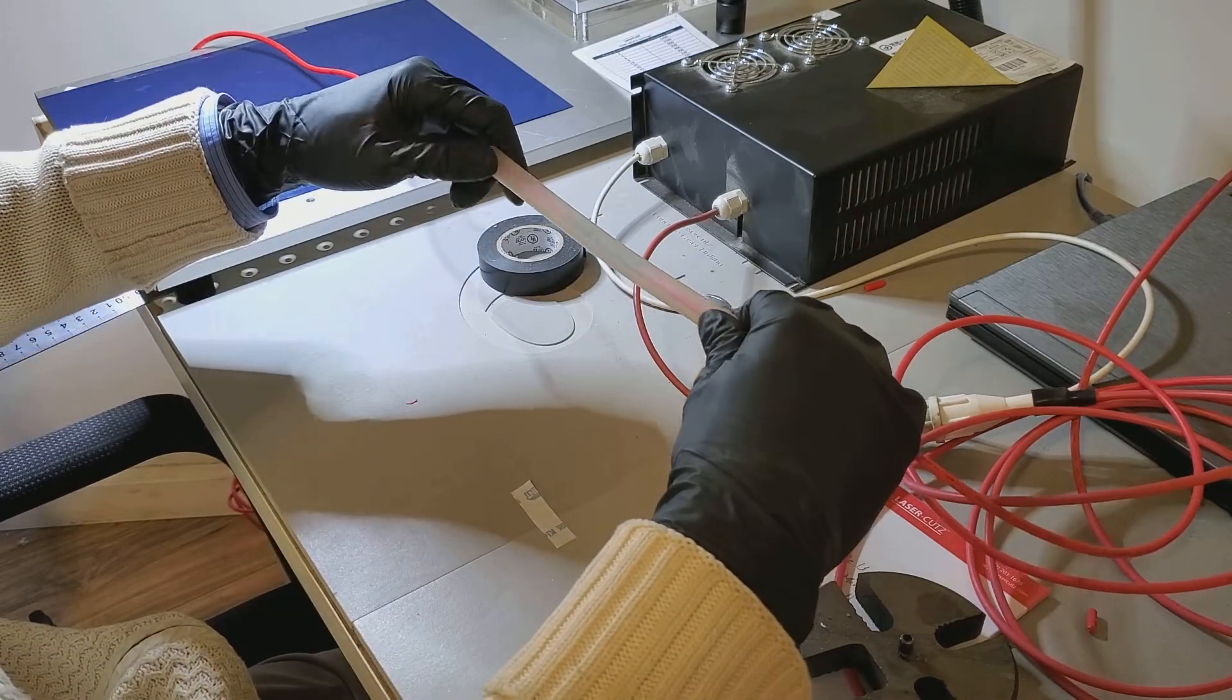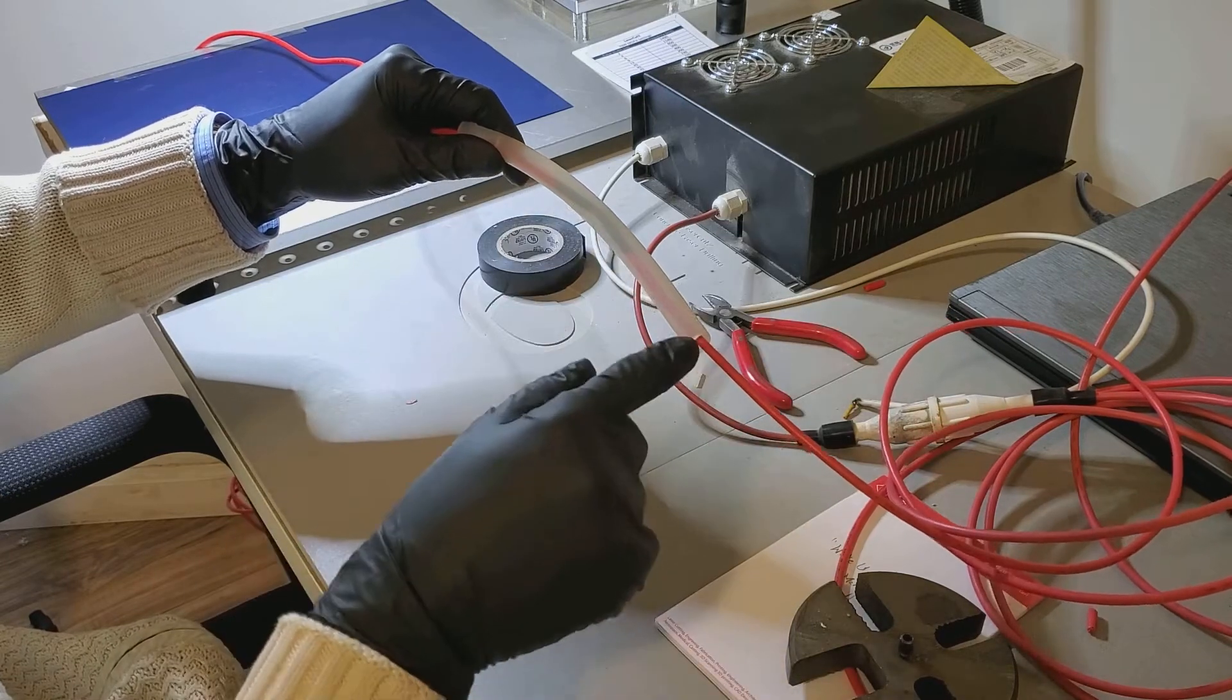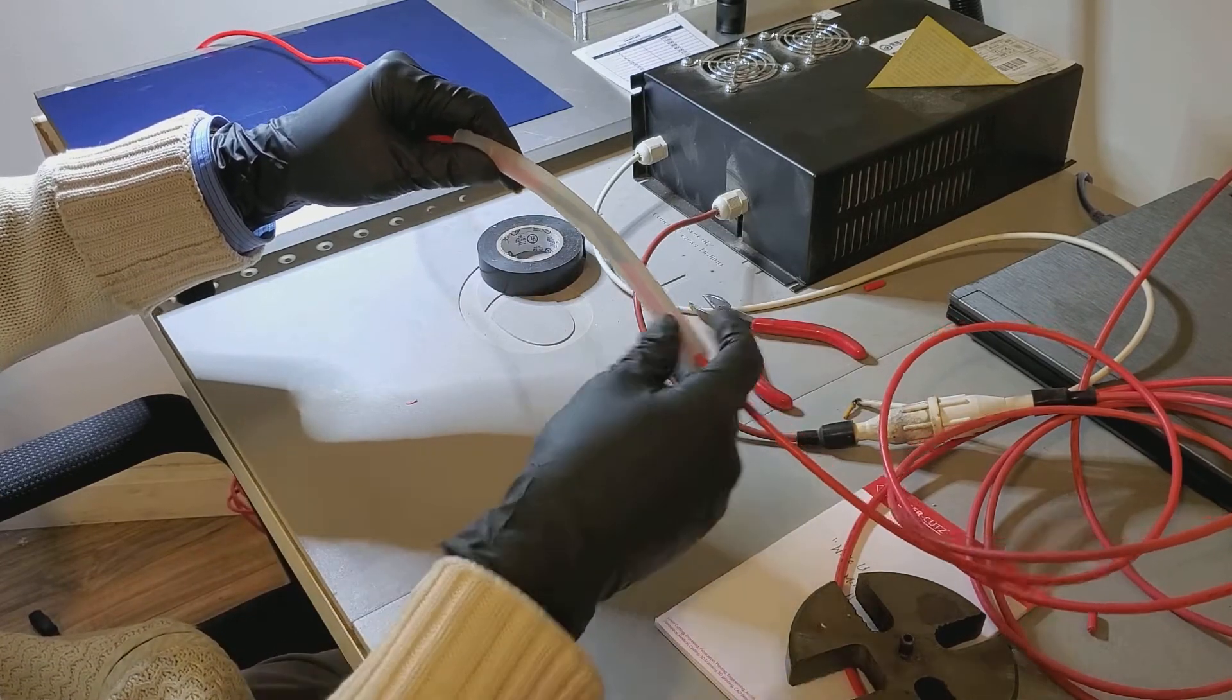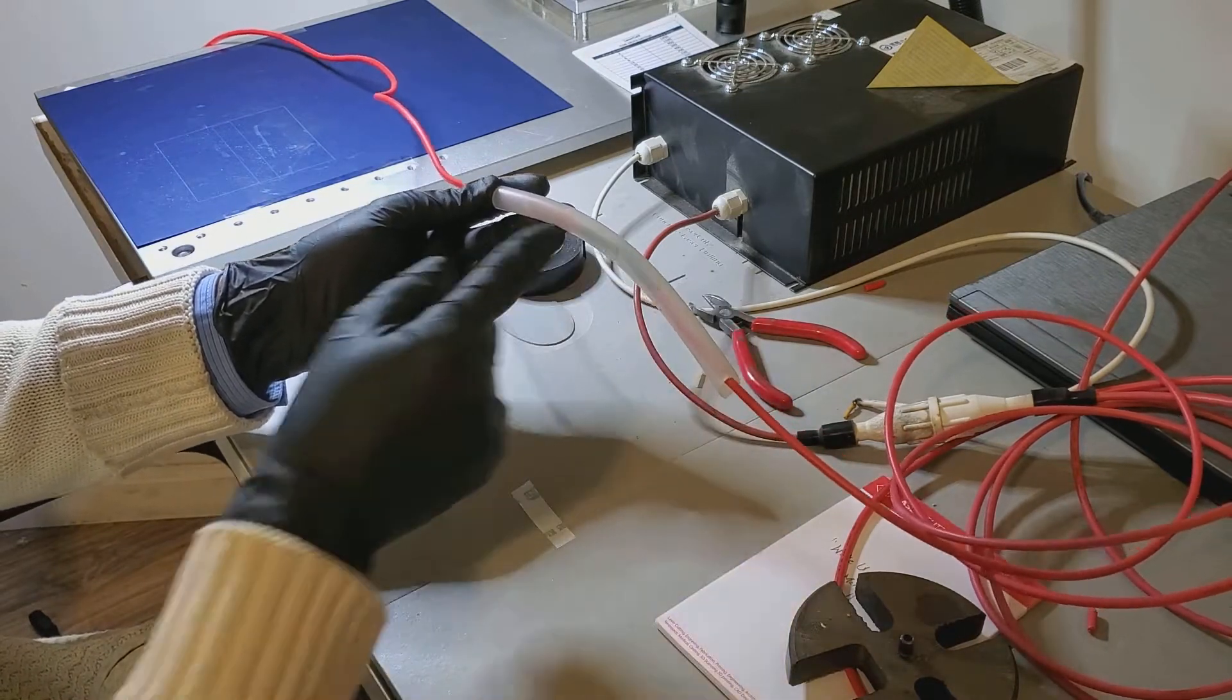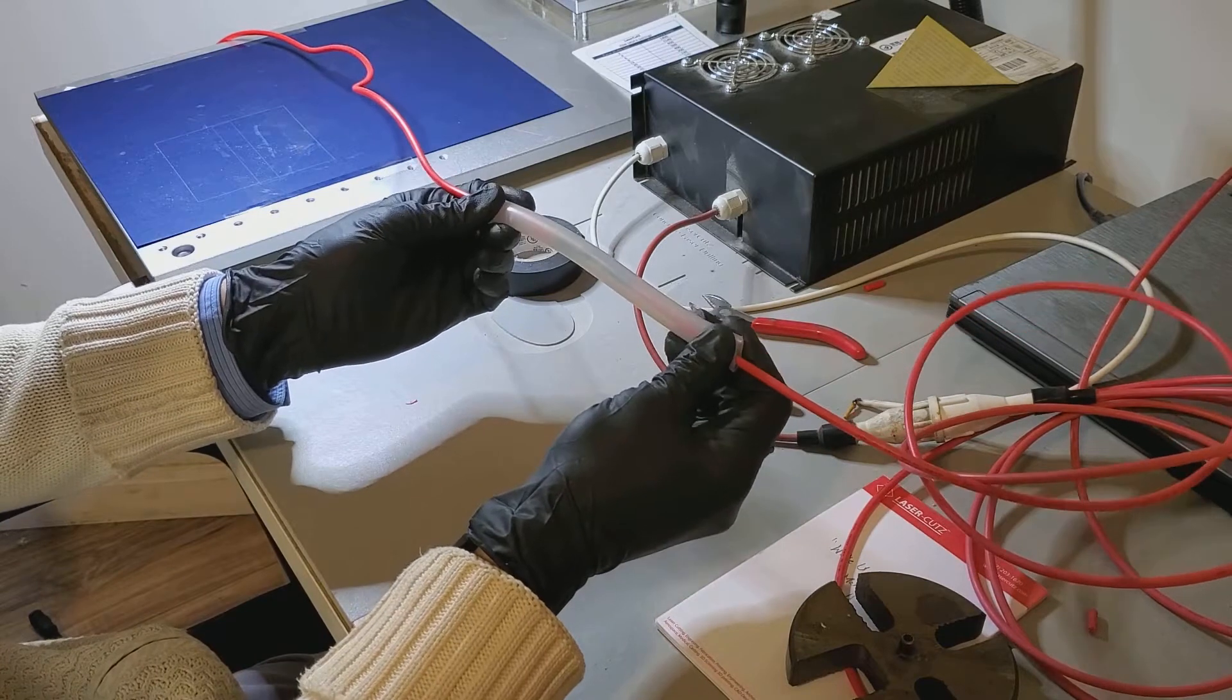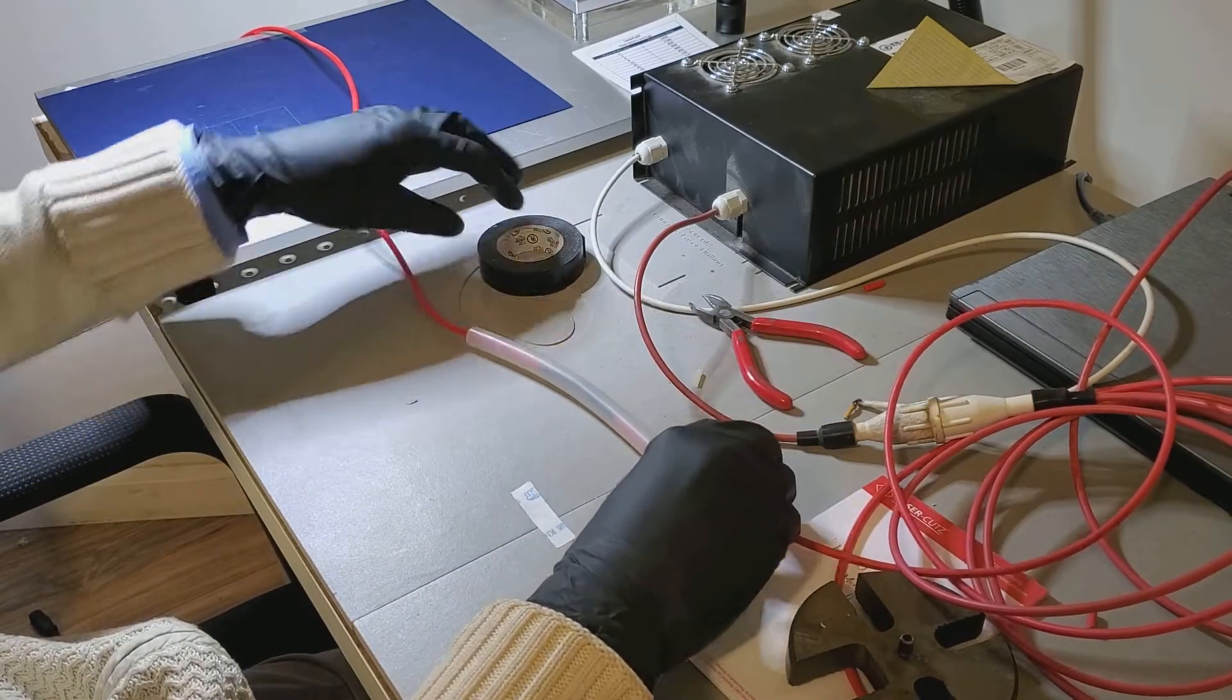I'm getting at least two inches—fifty millimeters—from the side, from the splice. That's sufficient enough to prevent arcing. So if there's an electrical charge, it has to go here and then get to the body of the machine or any grounding, which is a little harder than having a straight connection. So in most cases, it saves you from any arcing. Once I have the silicone tube in position, I'm going to use another electrical tape on the side, and that's going to give us another insulation form from water and moisture and extra protection.